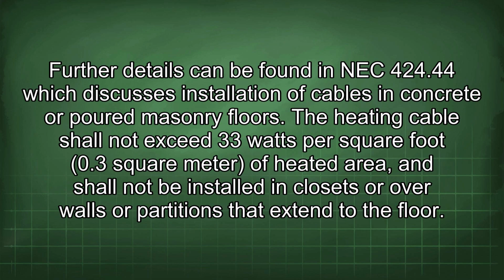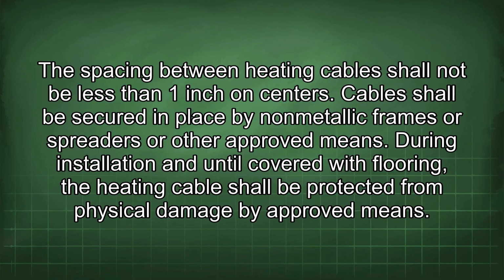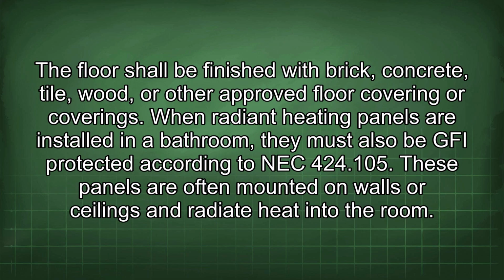Further details can be found in NEC 424.44, which discusses installation of cables in concrete or poured masonry floors. The heating cable shall not exceed 33 watts per square foot, 0.3 square meter of heated area, and shall not be installed in closets or over walls or partitions that extend to the floor. The spacing between heating cables shall not be less than 1 inch on centers. Cables shall be secured in place by non-metallic frames or spreaders or other approved means. During installation and until covered with flooring, the heating cable shall be protected from physical damage by approved means. The floor shall be finished with brick, concrete, tile, wood, or other approved floor covering or coverings.